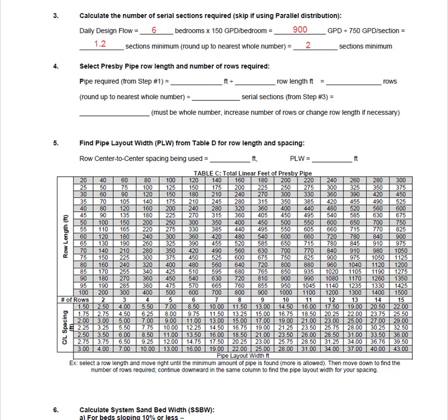Now let's determine our pipe row length and how many rows we will need. We're going to pull the value from step one — 420 feet of pipe — and divide by the row length we have selected. The rows should be as long as the site will accommodate, with a maximum row length of 100 feet. For this example, we have selected a row length of 70 feet. Dividing our total required pipe by 70 feet, we find that we need six rows. We then divide this by the number of required serial sections from step three, which was two. We will need three 70-foot rows in each of our two required sections.